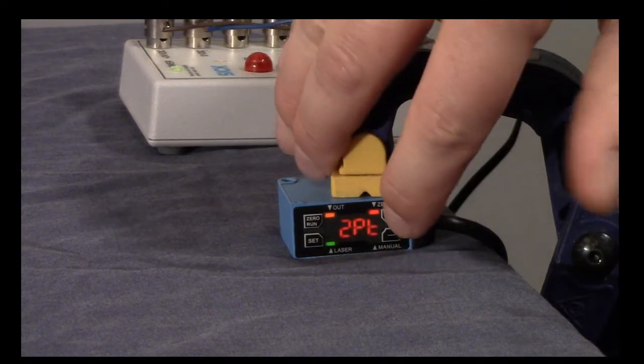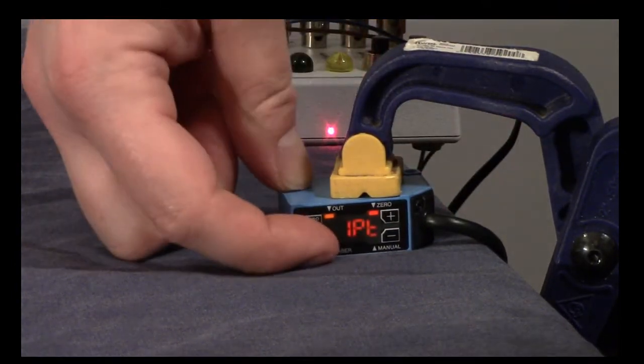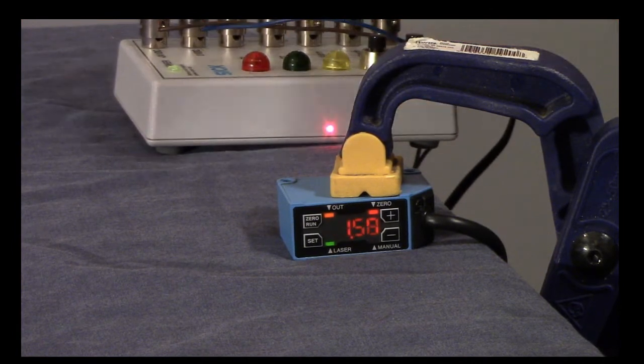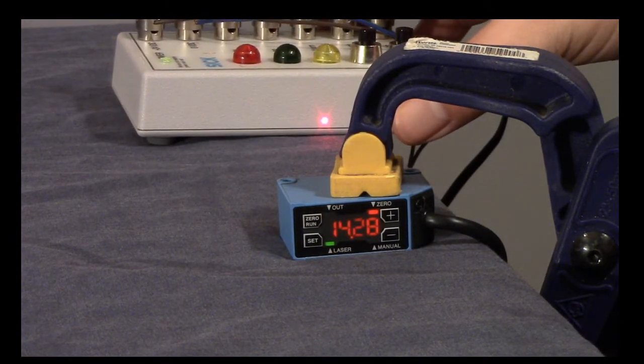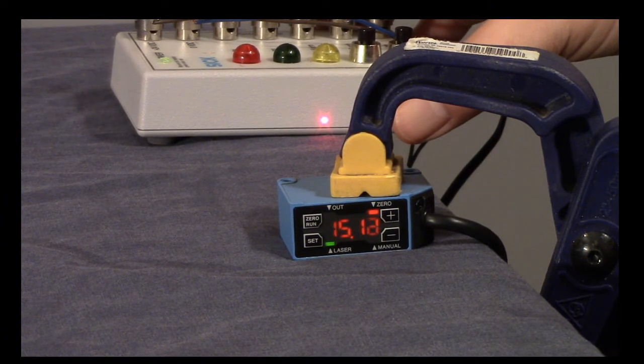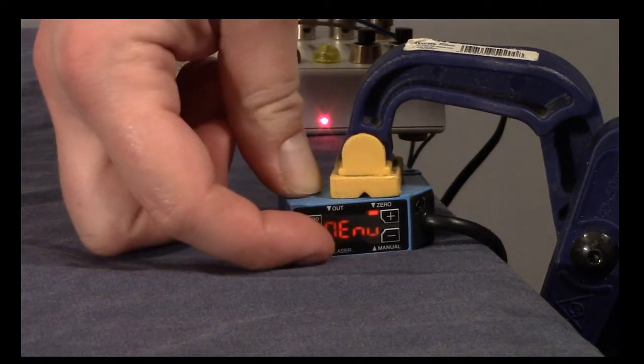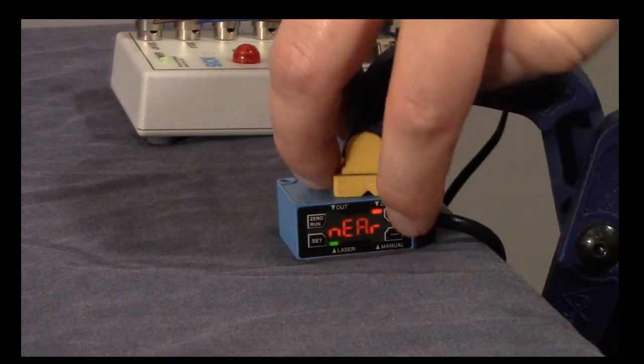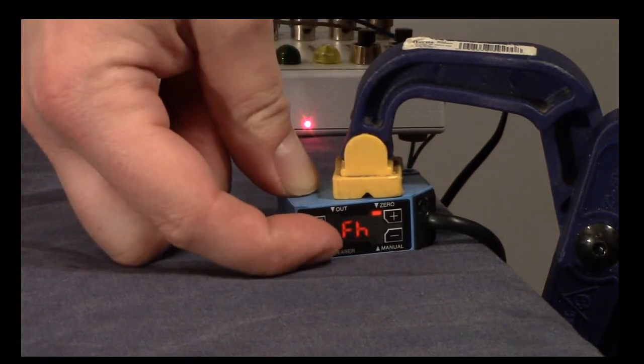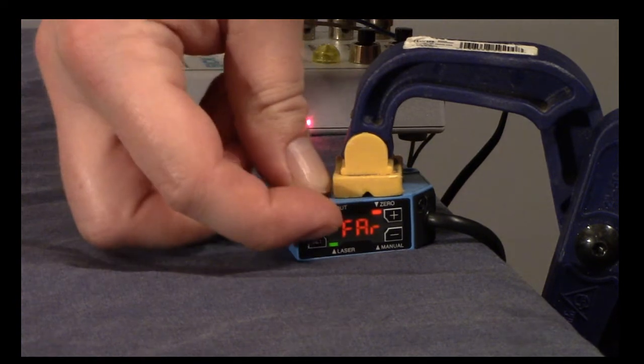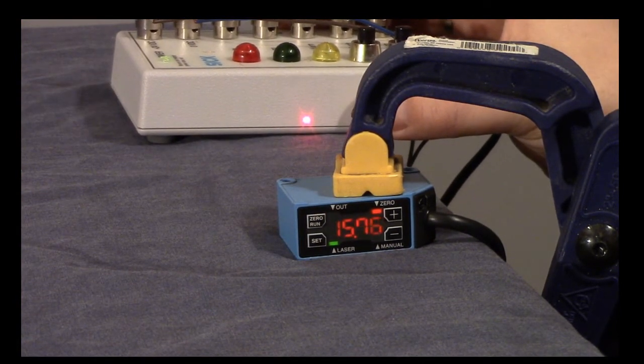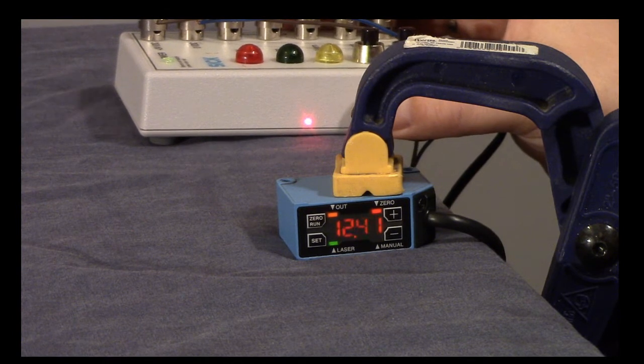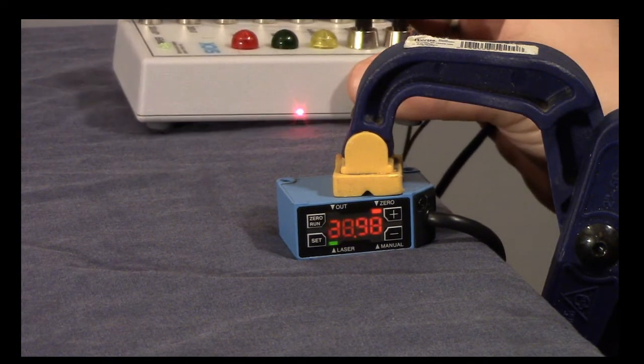So what we have seen here is going in setting up the sensor near the zero point and going in making the change for the mode to be the one point teach. And we're going to move it around a little bit. We're just going to find a set point and we're going to look at that light that that amber light at the top left turn on off. I'm just going to find some point here. Okay, I guess it's going to be 15.07. And we're going to go in, hit the set button, go into menu, and we're going to go and change that far setting because we're doing a one point teach. So move it to far, hit the set button at the distance we want it. It says teach, says yep, it taught, it's done. I'm going to go back and hit run, and I'm going to move it. And when I get closer than the top distance, the output turns on, the output light turns on. And we can change that to be normally open or normally closed or a high low output on the wire. But that light will always indicate that you are at your top distance or closer.